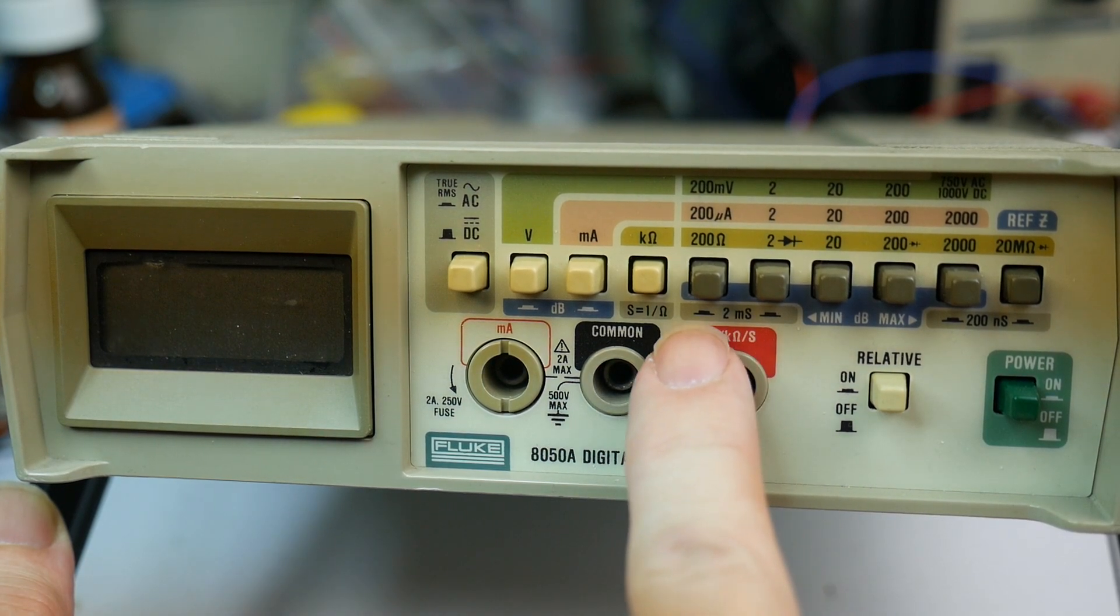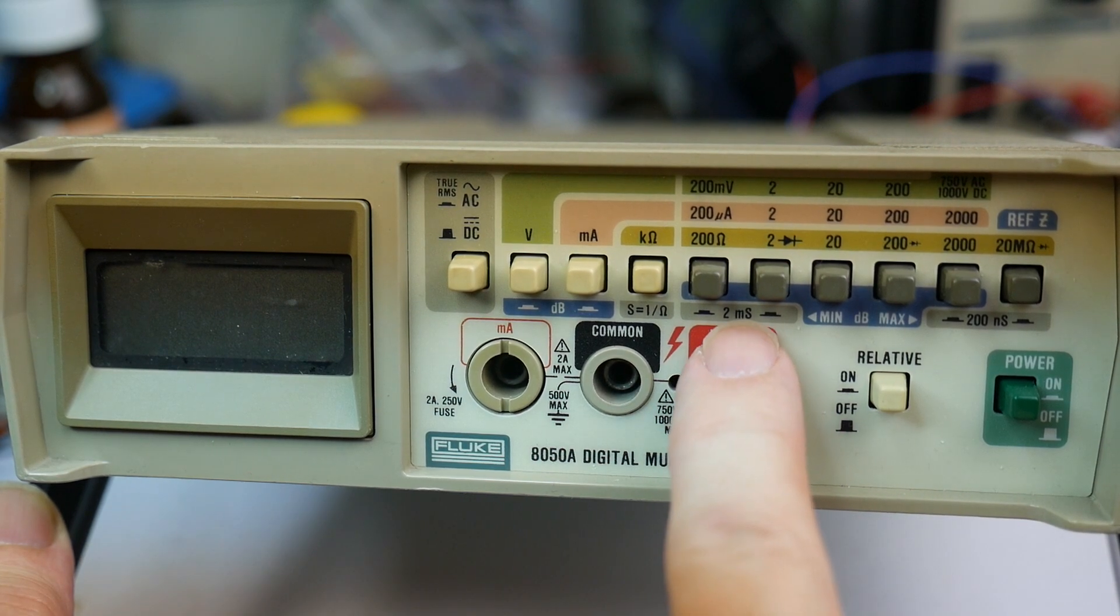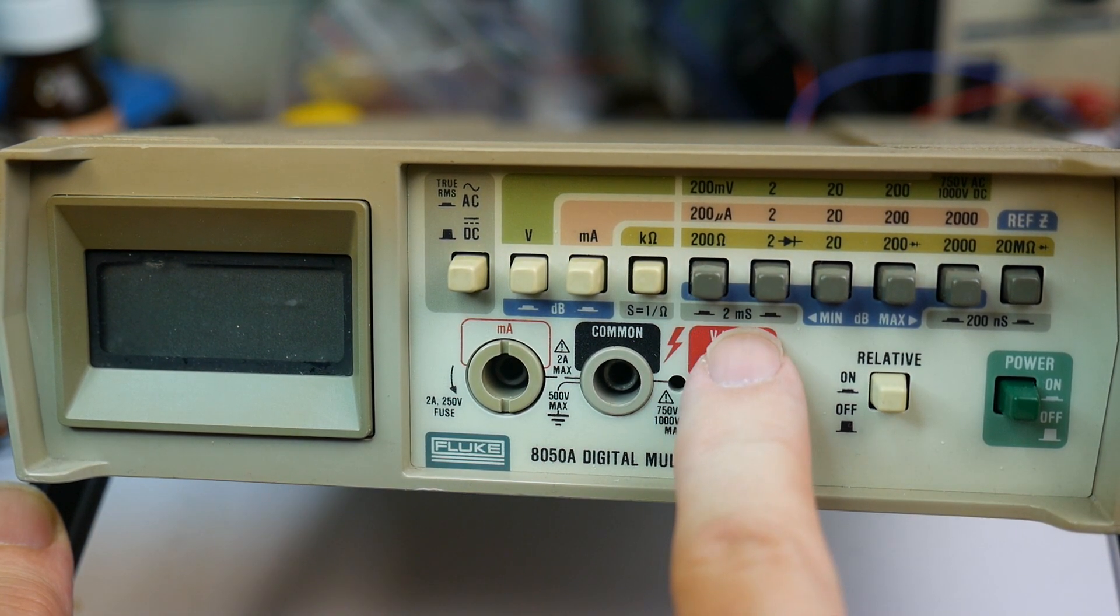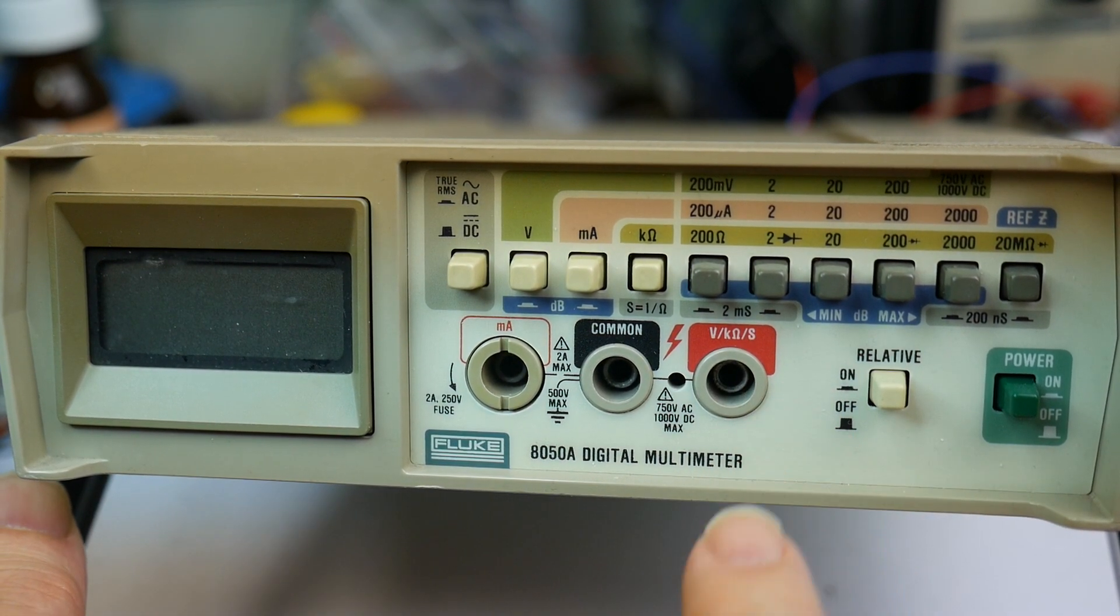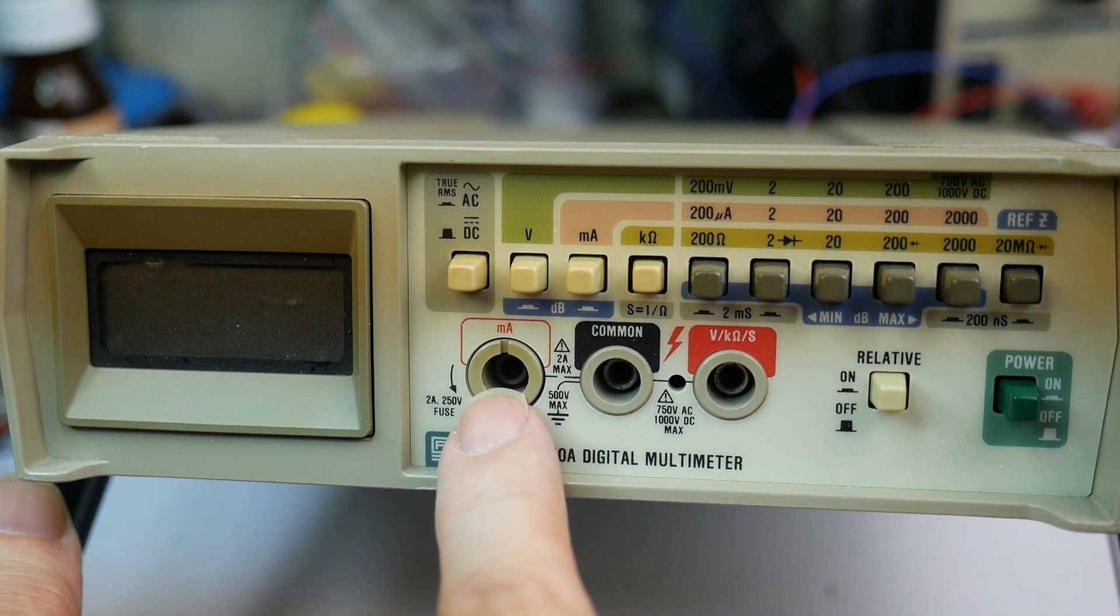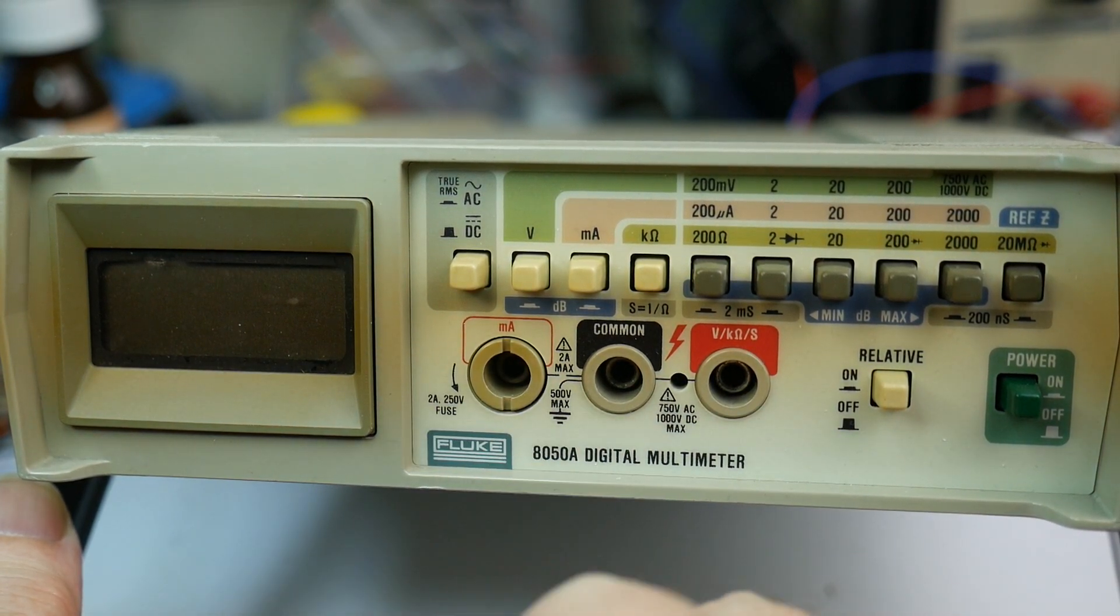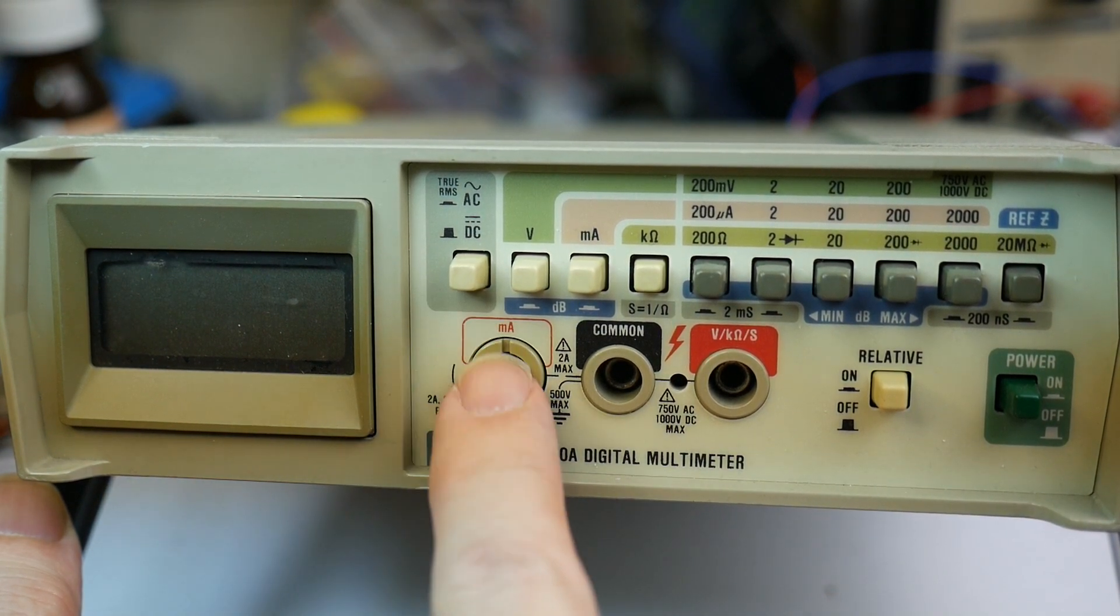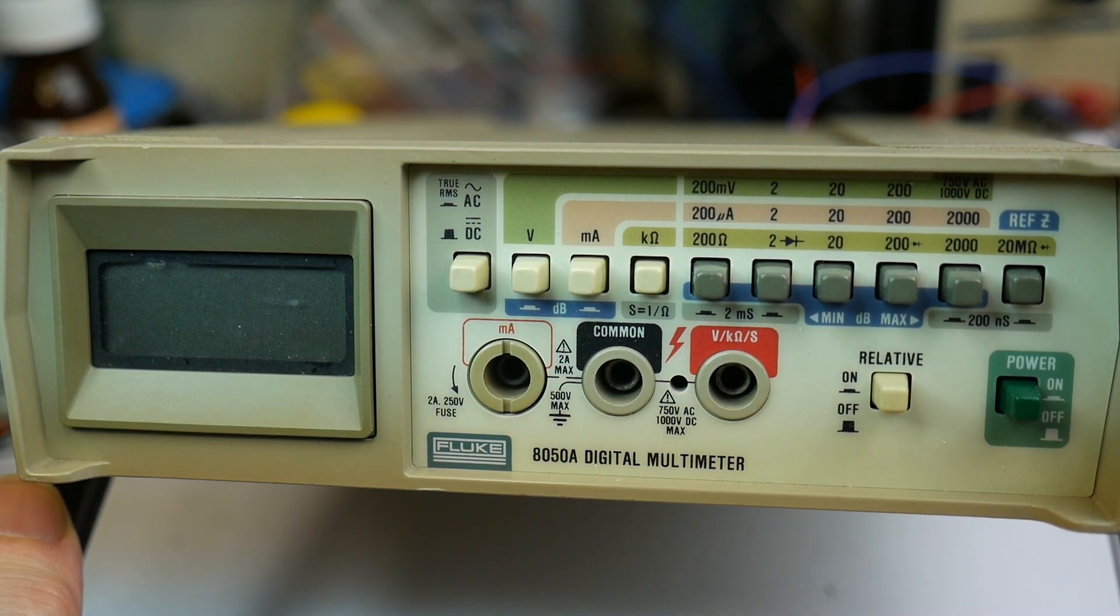It has a mode for conductance, which is this capital S for siemens. Not seconds—it's capital S. If you push both those buttons, you get millisiemens, which is a unit of conductance, one over ohms. There's a fuse holder behind the milliamp terminal or socket. There's a little screwdriver slot there you can unscrew or unbayonet, and there's a 2 amp fuse behind there that will blow if you put more than 2 amps through the current ranges.